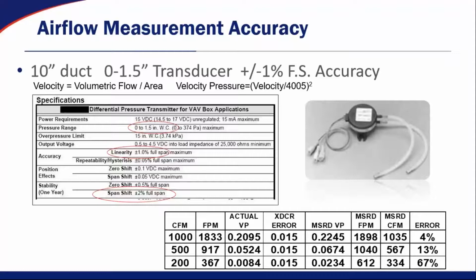But now if I try to get a 2-to-1 turndown ratio out of that same device, I go from 1,000 to 500 CFM. My velocity drops down to 917. My actual velocity pressure, which is 917 divided by my constant of 4,005 squared, is 0.0524. And my fixed transducer error is still there. So when I add my transducer error to my actual velocity pressure, my measured velocity pressure now is 0.0674. Measured velocity is 1040. Measured CFM is 567. So now at a 2-to-1 turndown ratio, I dropped from 4% error up to 13% error, which could put you outside the realm of being able to control differential pressure or offset inside of a space.